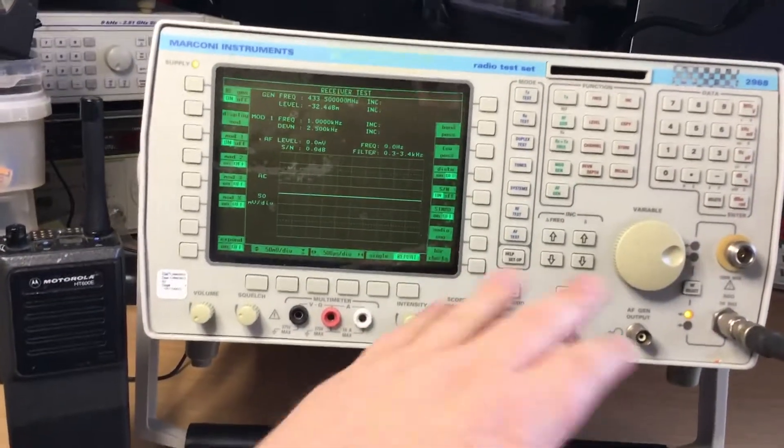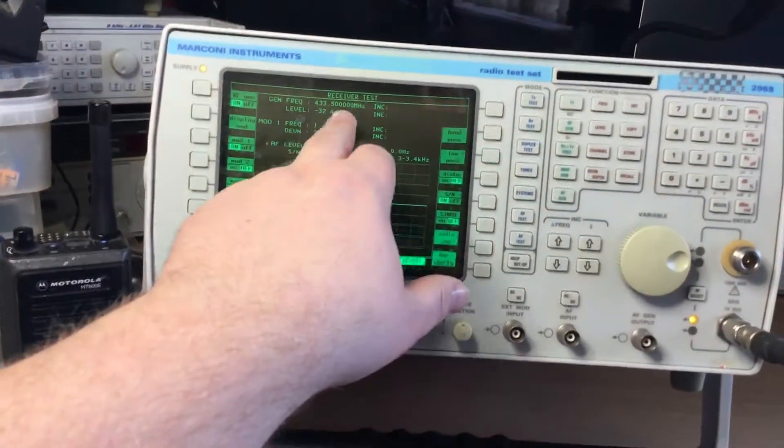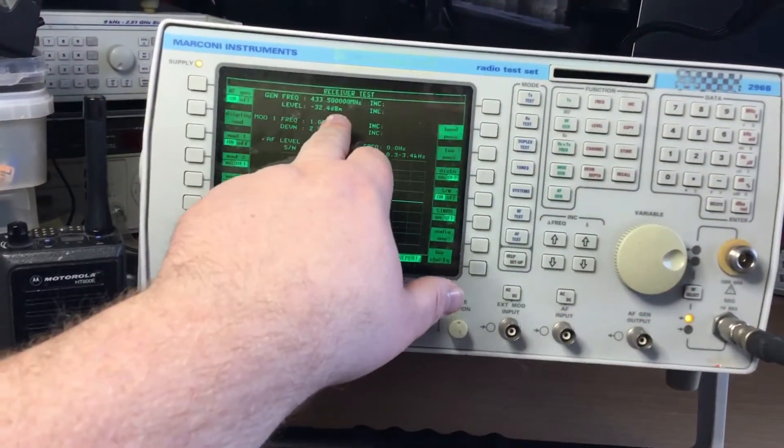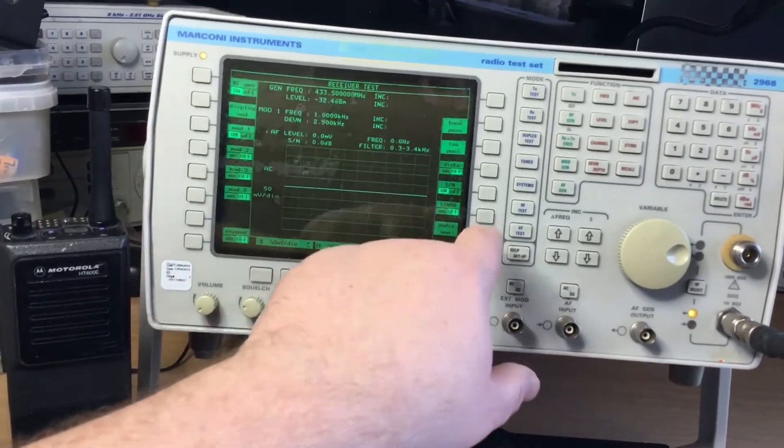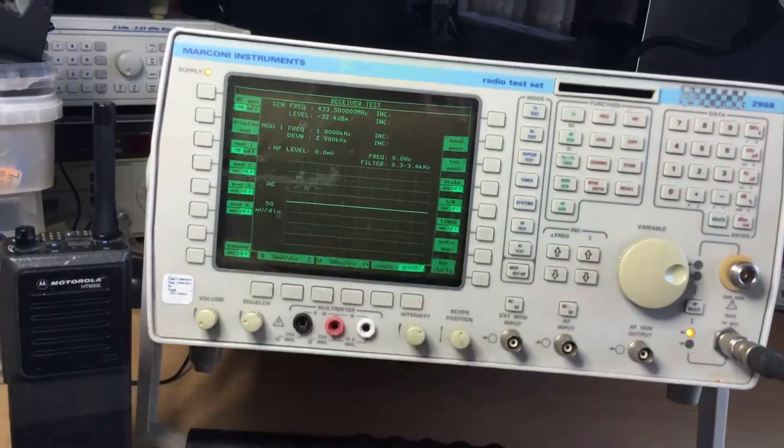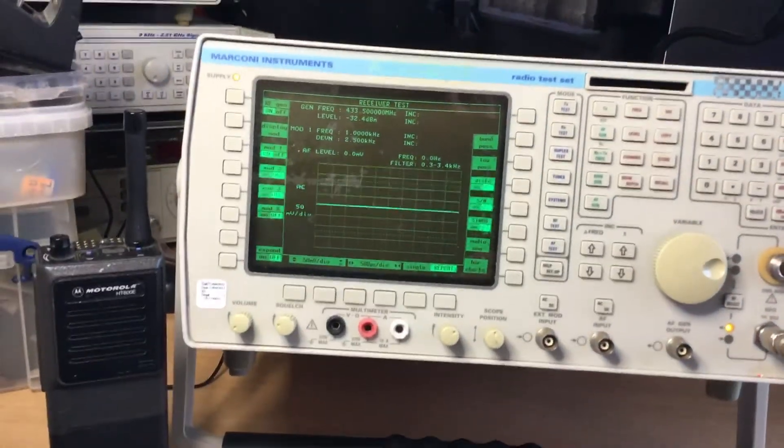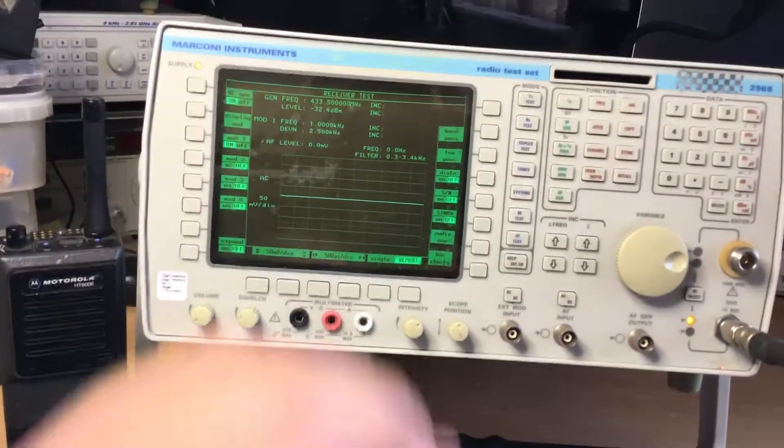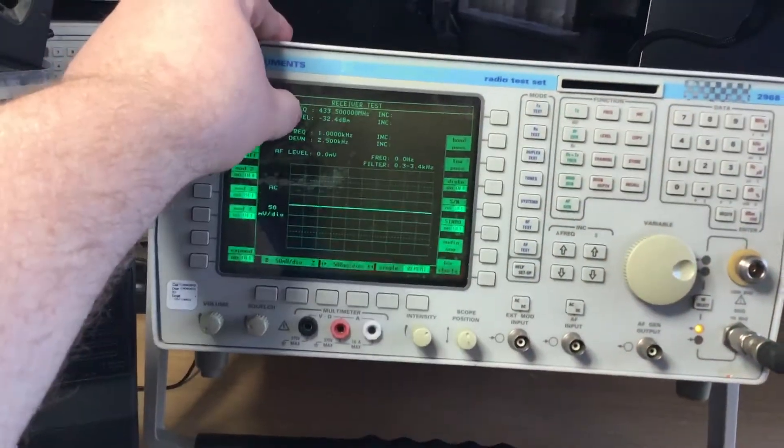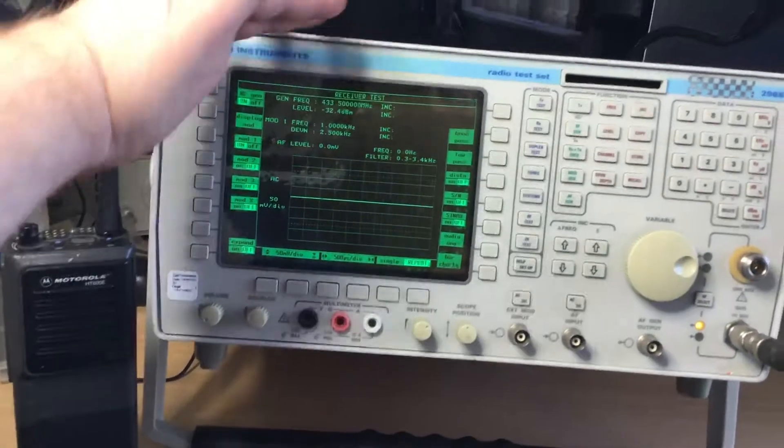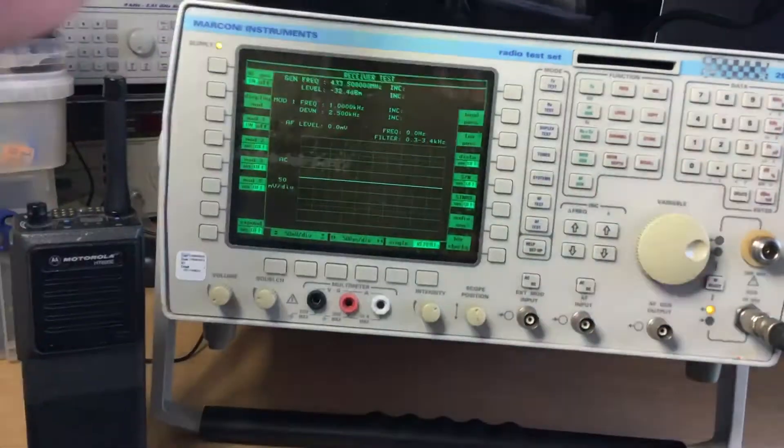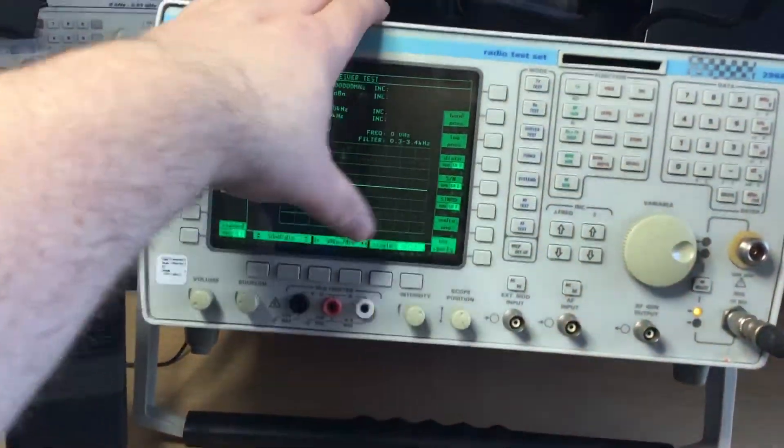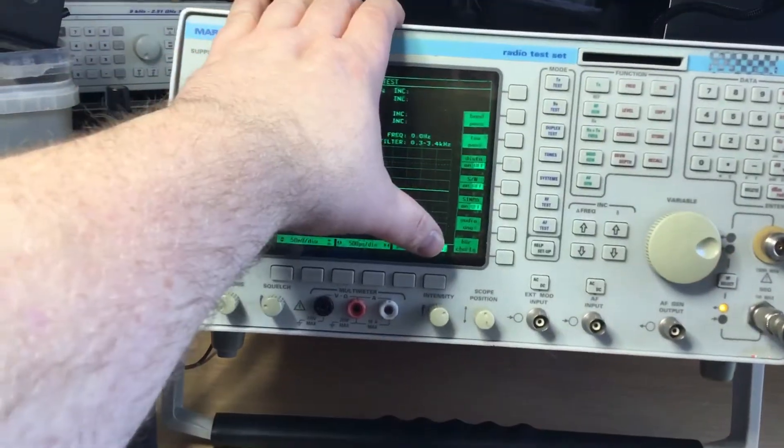The receiver at a certain spec which is denoted in the service manual for the radio, with the RF level, must reach a certain RF level and be above a certain specification for signal to noise.